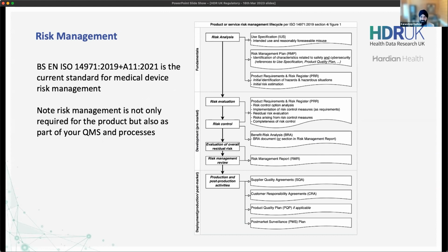So if you look on the right, look at your risk analysis. Have you noticed it starts with the intended use statement? So that's what we keep talking about. Your intended use statement is where everything begins. Once you know your intended use, you realize what is the foreseeable misuse. Who is the person that's going to be using it? Are they super qualified? Is it the lay user? And then straight away, you can start identifying the user risks.